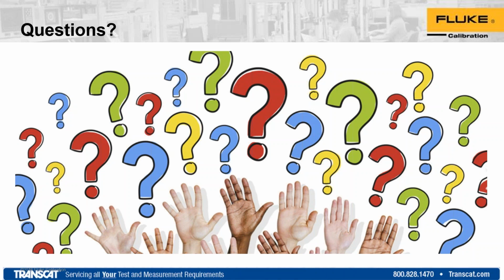Okay. The next question is related to that. If the probe is a 0 to 140 C temperature and the field process temp is not more than 90, do you need to test the probe also at 140, or can you test it only at 120 and say that it's okay?